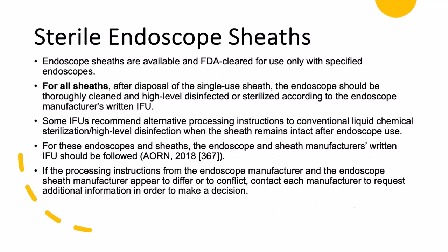Many manufacturers have sheaths for endoscopes. For all sheaths, after they're disposed of, the endoscope should be thoroughly cleaned and high-level disinfected or sterilized according to the IFU. Now, some IFUs recommend alternative processing instructions to liquid chemical sterilization when the sheath remains intact after the endoscope is used. For these endoscopes and sheaths, the endoscope and sheath manufacturer's written instructions should be followed.